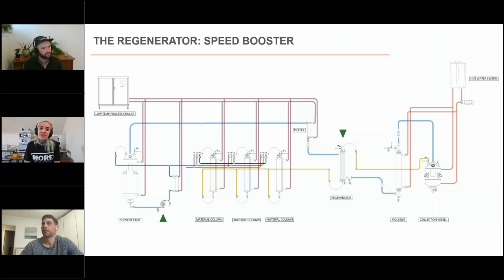If I could make a recommendation: if you're running an ETS system with those coil-inside-a-coil heat exchangers, just swapping that out for a plate exchanger makes an incredible difference in how your system operates - even if you're still too scared to get rid of the recovery pump, or can't afford a liquid pump, or can't change your chiller. If you can only make one change, trade the coil for a plate exchanger, because of the efficiency, and because those coils need to be thawed and blown out with an air compressor pretty often.